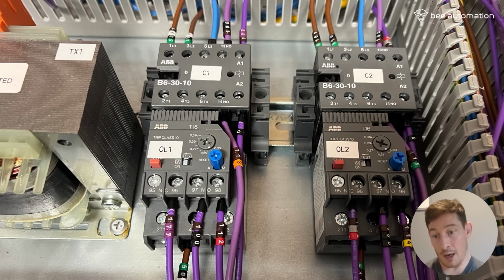So that will then be coming out of T1 off to the terminal block, and similar with the neutral, out of T3 off to the terminal block. So that's the power going to the pump. We've got our normally closed contacts here. So we'd have a supply of, in this case, 24 volts AC. I've not done that yet because that's coming from the door. That'll be coming in here, normally closed, out on 96, cable 177, which you can see loops round to here, A1. So when that's in a good condition, that's closed, things haven't tripped, everything's healthy, power can pass through that and into A1, energizing this contactor, and this is obviously going to 0 volts on A2.